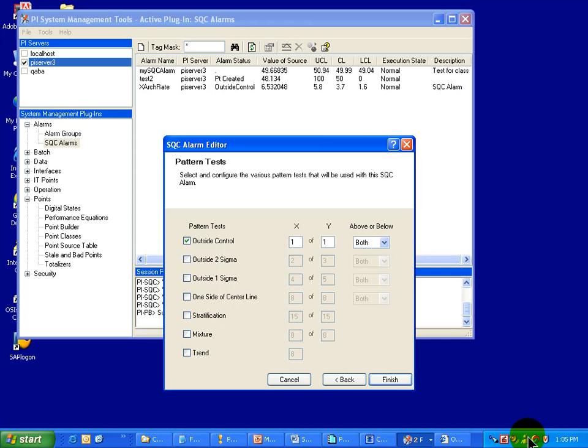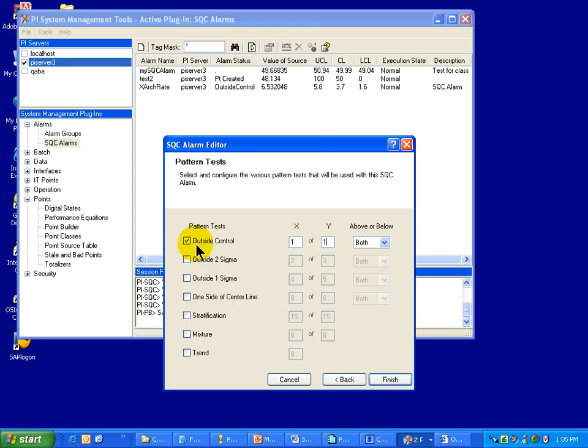On this screen you can choose which of the standard Western Electric alarm tests you're going to put into place. As you can see, it defaults to a single alarm type — the 1 out of 1 instances of a source tag outside 3 Sigma. That's outside control. 1 out of 1 means we simply need one value to go outside the 3 Sigma, either above or below the center line, and we generate an alarm.